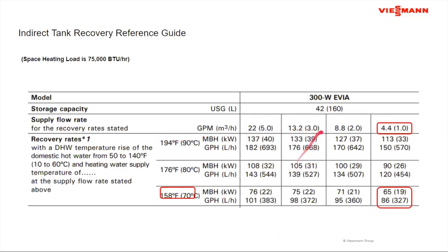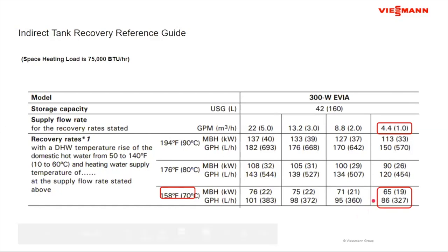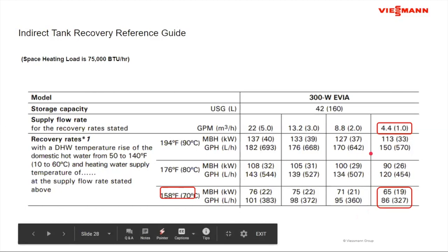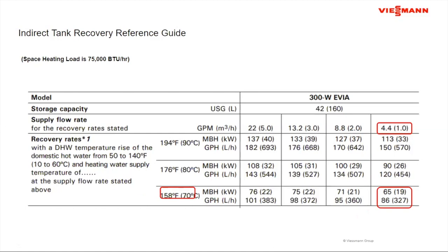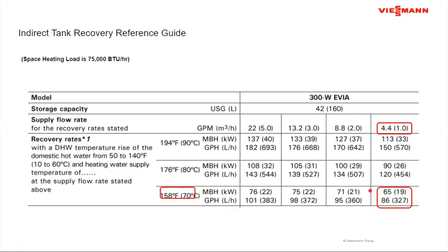And these are continuous numbers. Excuse me, I want 51 gallons continuous flow. These are continuous numbers. So the lowest performance I have here is producing 86 gallons of hot water. So for 86 gallons, I need 65,000 input. I need 4.4 gallons per minute, and I need 158 degree water temperature. So I know going in there, I'm going to size the pump for 4.4 gallons per minute. I'm going to provide a water temperature of at least 158 degrees, and I know I'm going to get my 51 gallons per hour. In fact, I don't even need 65,000 BTUs. I only need 33,000 to get the 51 gallons that I'm looking for.